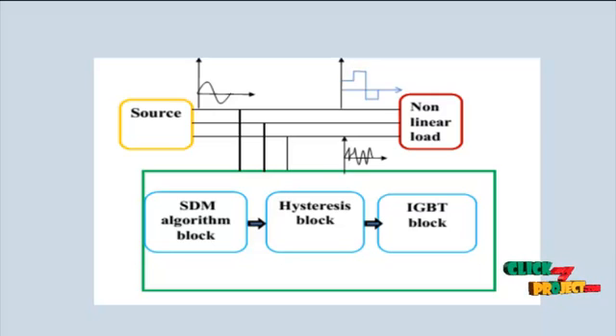These non-sinusoidal currents contain harmonic currents that interact with the impedance of the power distribution system to create voltage distortion that can affect both the distribution system equipment and the loads connected to it.